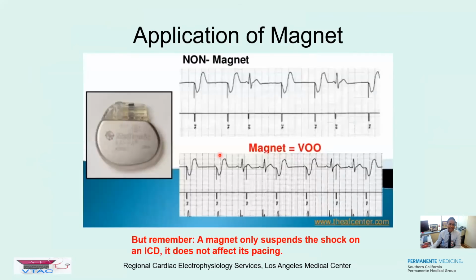What a magnet does is basically change it to asynchronous. So you see, this is a normal pacemaker. It's pacing, it sees a QRS, it says I'm going to stop. And it paces - it sees it's going to stop here, it paces right on through. Don't worry about pacing on T waves, that's another discussion, it's probably not enough energy to cause harm.